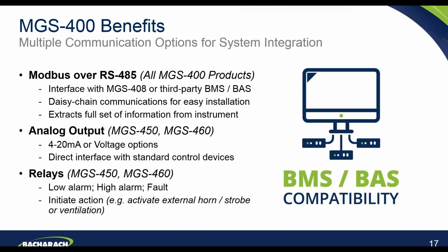From a communications perspective, again, the benefit we wanted to add here was to provide some degree of flexibility for our customers. So all MGS-400 products feature Modbus over RS-485. So that enables the detectors to interface with the MGS-408 controller or any third-party BMS system that utilizes Modbus. The use of this also enables us to offer daisy chain communications to make for easy installation of the product. And the Modbus extracts a full set of information from the instruments around the alarm set points, the diagnostic information, sensor information, calibration data, etc.